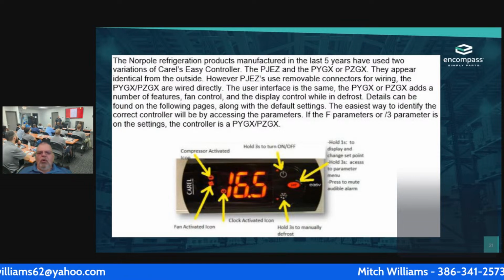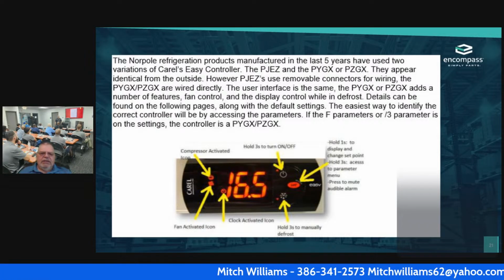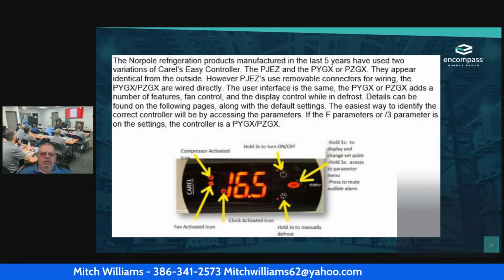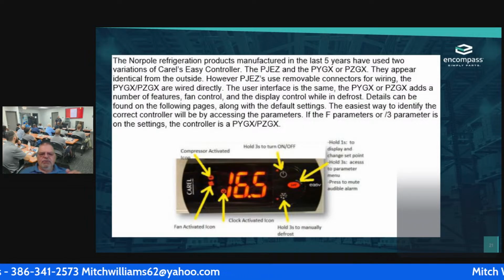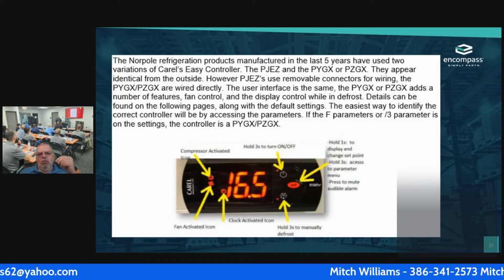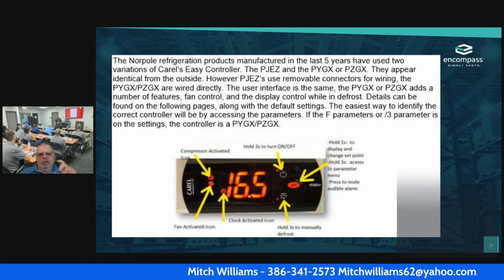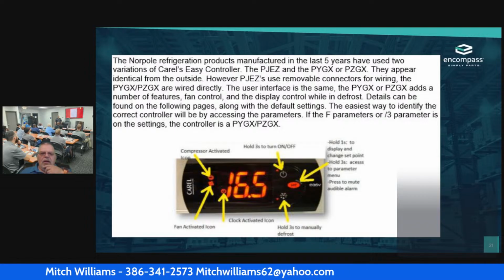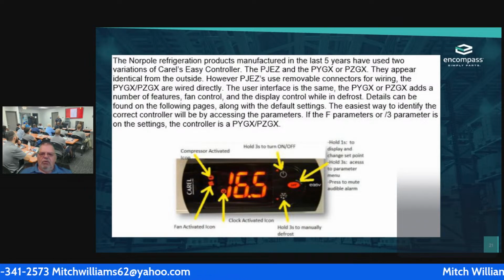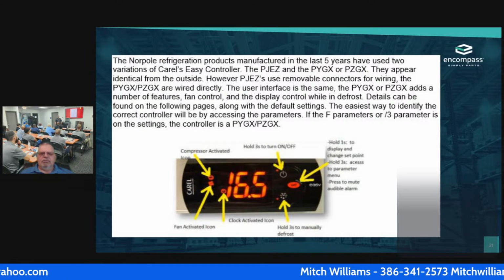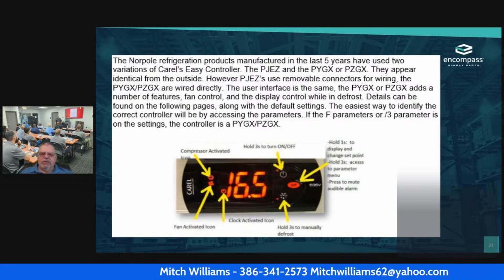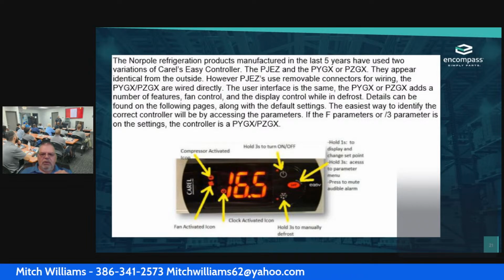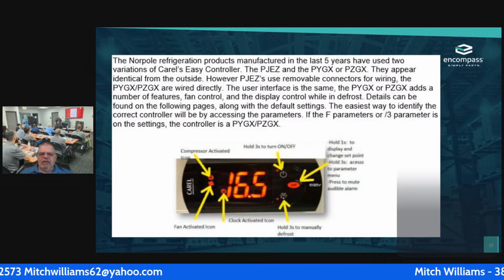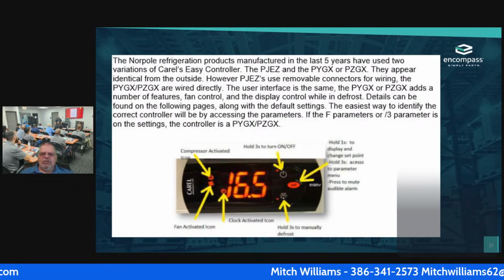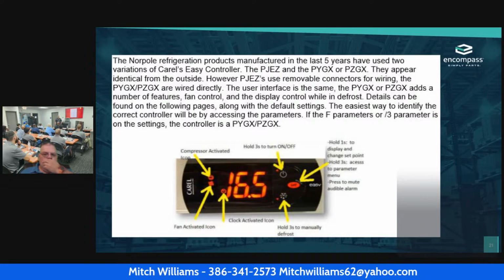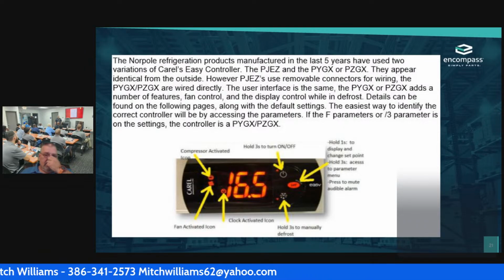So the display, what does it tell me? Right, if you look at this, it tells me that the compressor's on the far left side. Okay, it also tells me that the fan is activated. So this one, while the fan is running, when the compressor's on, the fan's on. Okay, if I use the on off button there, I hold it and it turns it on. Hold it, turns it off. If I look down there, there's the red one that's on the far right side. That's the set button. To display the set point, hold it for 1 second. If I hold it for 3 seconds, it gives me access to the parameters.